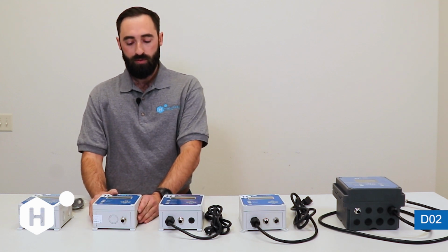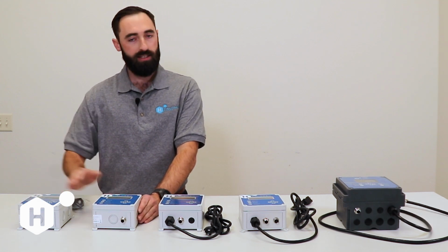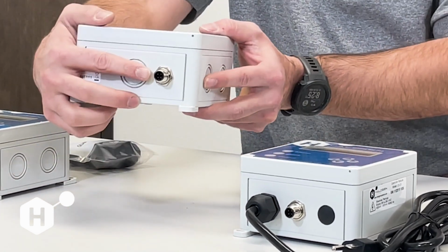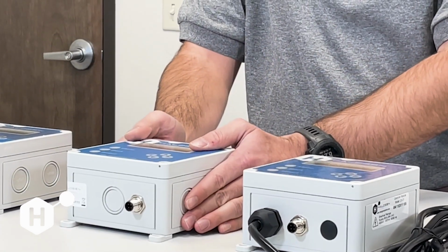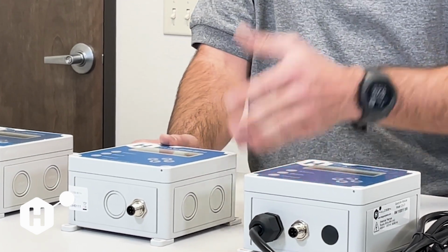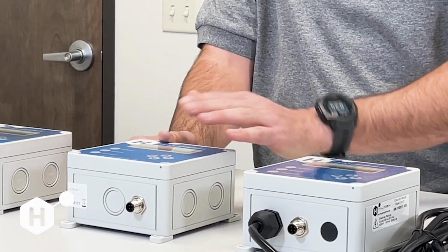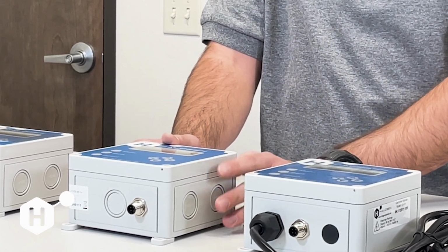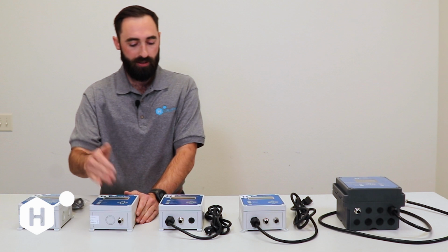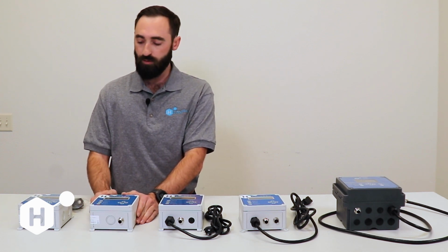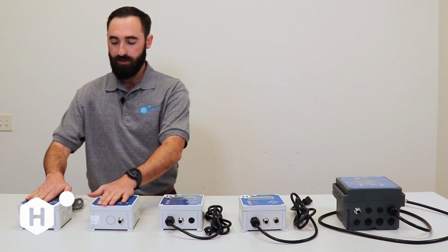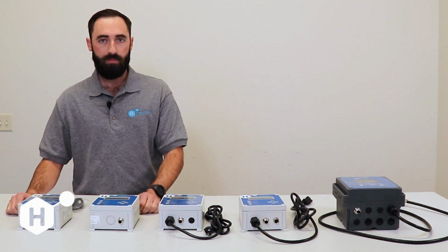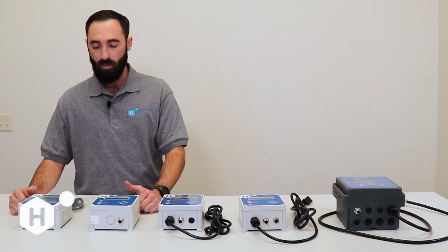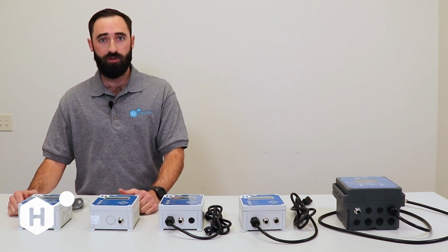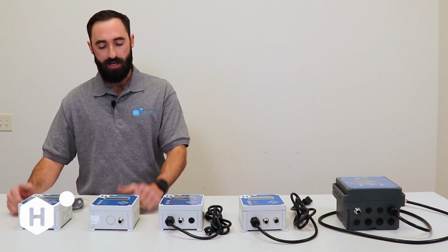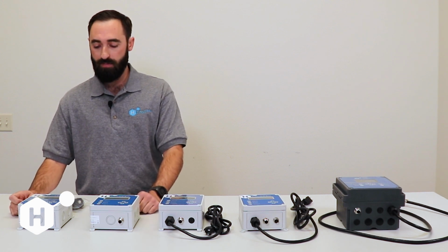Next, we have our D02. The D02 is almost the exact same as the D01, but as you can see, the primary difference is an included M12 sensor connector. This is great if you have facility power and are able to supply 24 volt DC power to the display unit, and then plug into one of our municipal sensors or a sensor that has an M12 connector. Both of these units have 4 to 20 analog outputs, are able to communicate with 1 to 10 sensors over Modbus, and then pass on that signal over the 4 to 20 analog outputs.